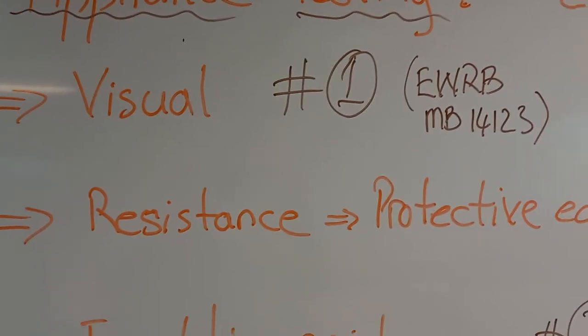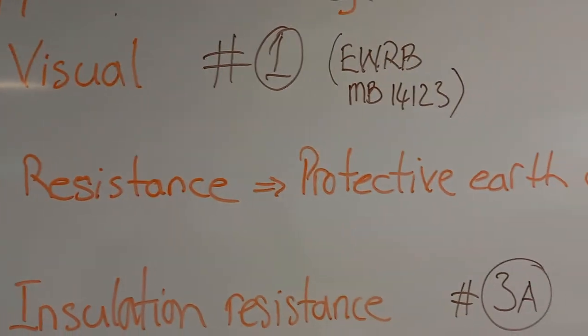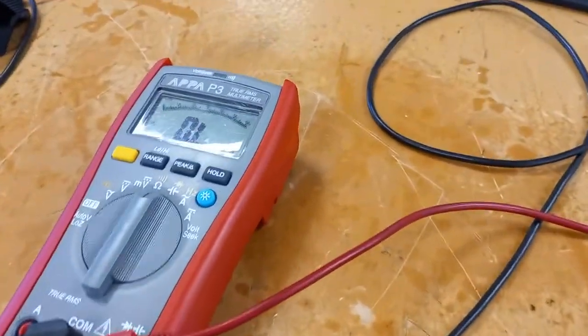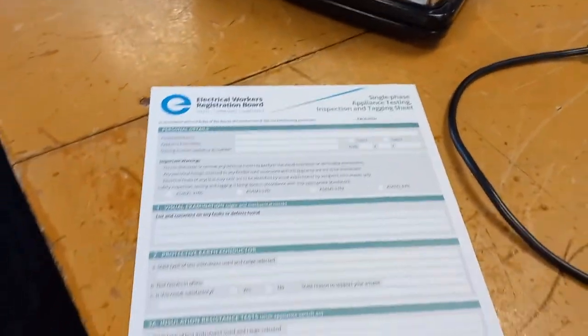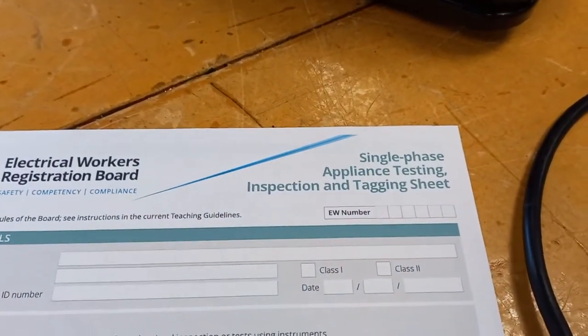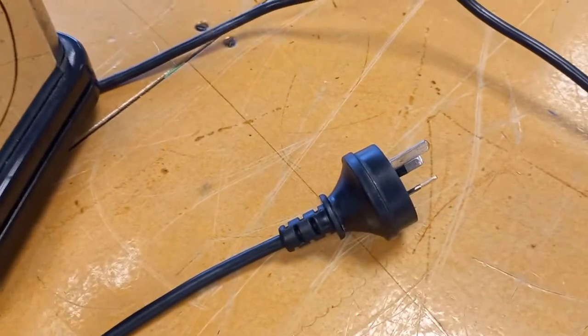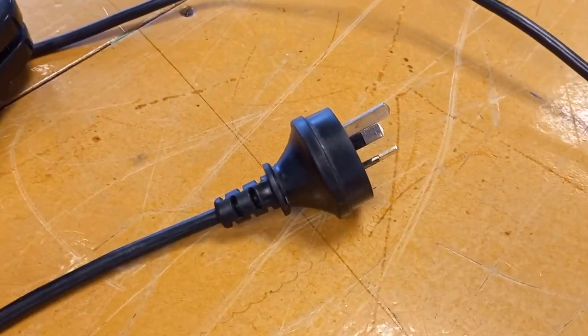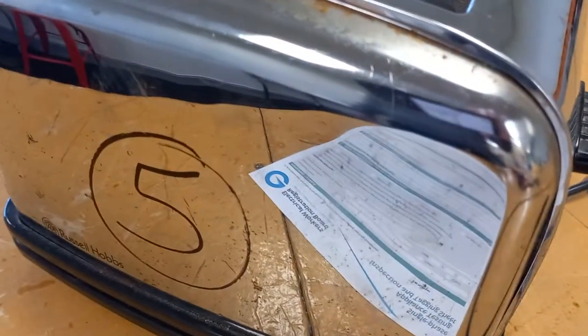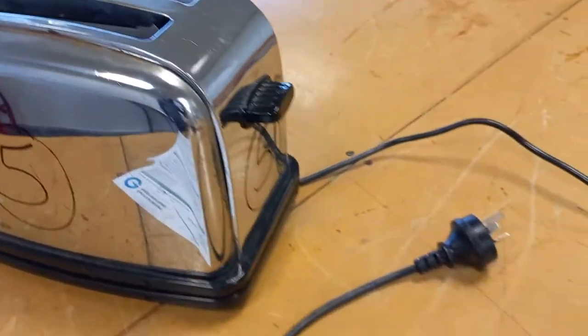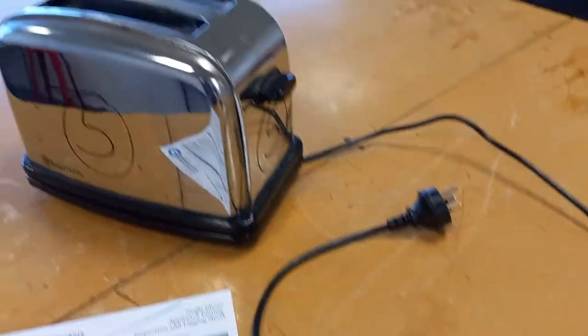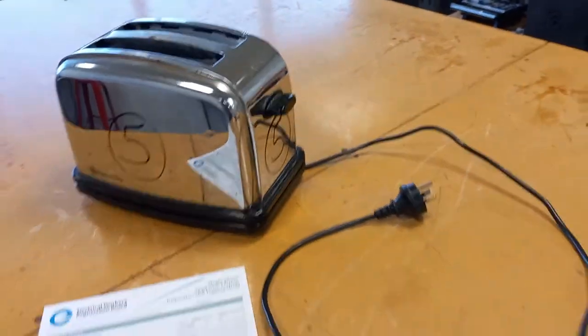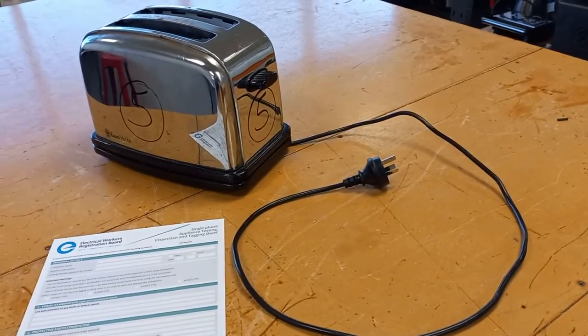Once that's complete, we move on to the resistance measurement of the protective earth conductor. This is done using an ohm meter on the low ohms range. The maximum resistance permitted by the EWRB on this training record form is 1 ohm. No more than 1 ohm is permitted from the earth pin on the plug to the metal casing on the Class 1 appliance. If that resistance is exceeded, the appliance is not safe and will fail the test. Typically, the resistance will measure about 0.1 of an ohm.